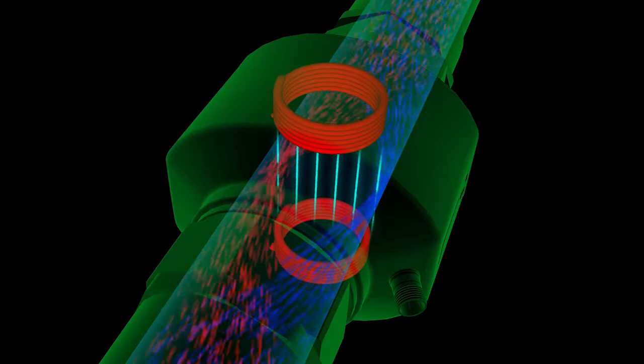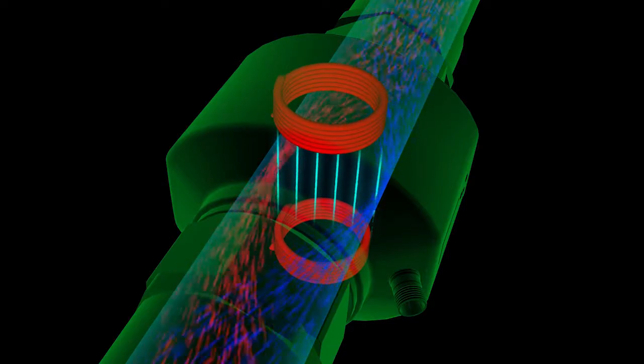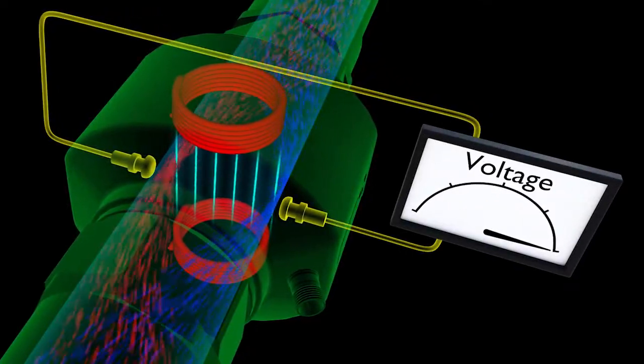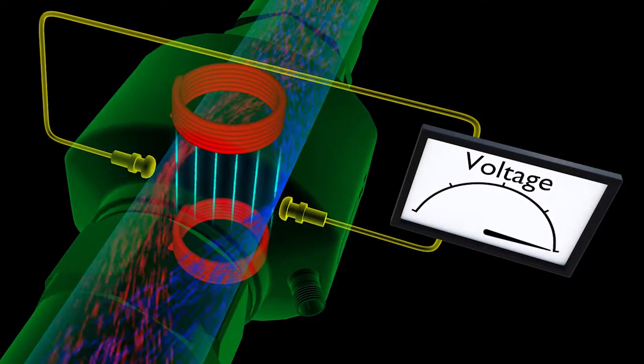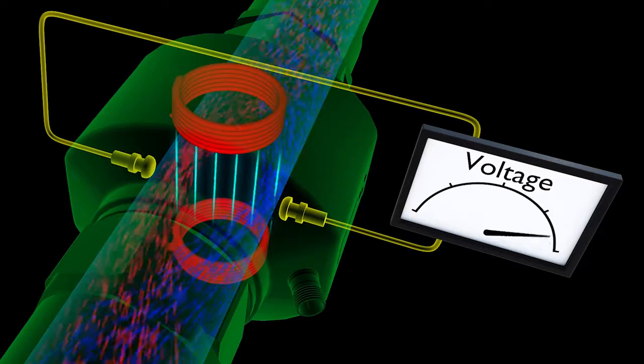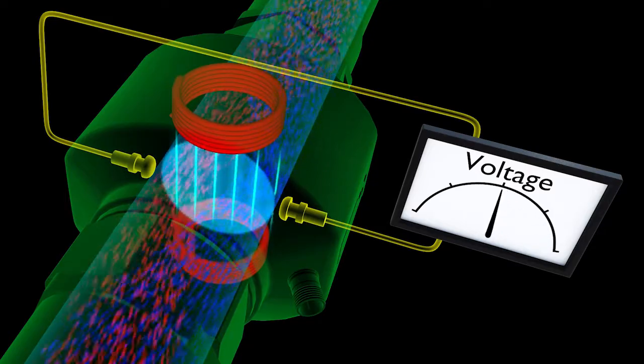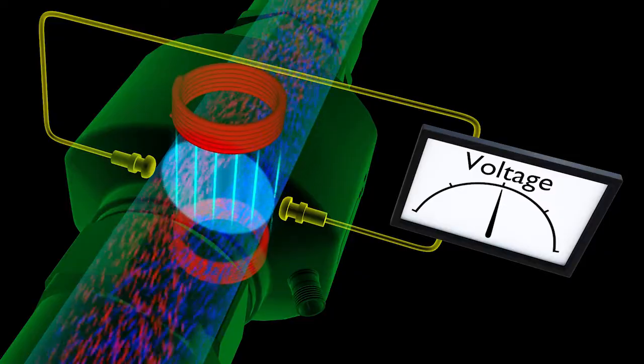The more the particles separate, the more the voltage differential. These electrodes embedded in the side walls are then used to measure the voltage created by the separated particles. And since that voltage is directly proportional to the velocity of flow and the cross-sectional area is known, the meter can calculate the total flow.